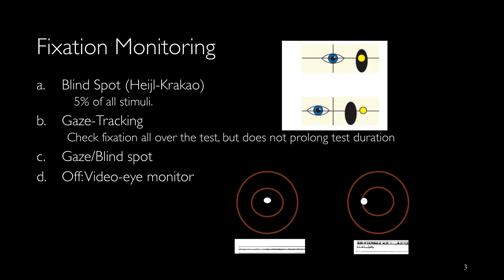The gaze tracking system checks the location of the corneal light reflex based on the pupil area. In a patient that has steady fixation all the time, the corneal light reflex is going to be at the center of the pupil. But if the patient moves the eye, the location will change and we will get some sort of deflection in the gaze graph. If the patient moves we'll get upward deflection, and if the patient blinks we'll get downward deflection.